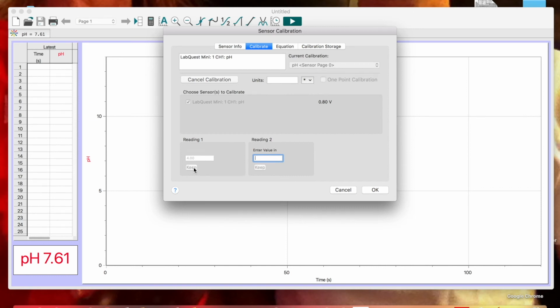For whatever reason, the pH of 10 usually takes a little longer to stabilize. So we're going to let this sit here for a bit, and I want to make sure that it gets a nice low voltage. A very common error here is to get impatient with this part of the calibration and not let this bottom out essentially. So I like to give this a 3 or 4 minute amount of time before it actually decides on what the final voltage is. So I'm going to prepare some other solutions while this thing finally decides on its lowest voltage. So we'll rejoin in a second.